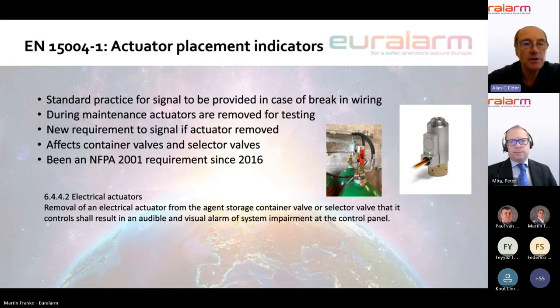Now, this has been an NFPA requirement since 2016. It was actually introduced into the 2012 edition of NFPA and was mandatory since 2016. So you can see the clause there, the wording in the clause, quite straightforward. Removal of an electrical actuator from the agent storage container valve or selector valve that it controls shall result in an audible and visual alarm of system impairment at the control panel. It's a mandatory requirement. You'll see there that it says shall, and that means it must be implemented.